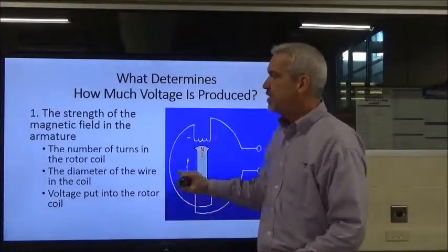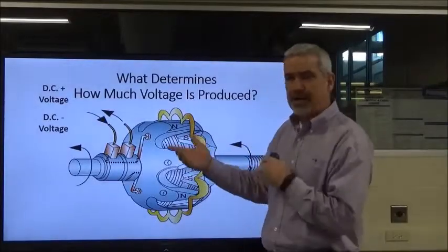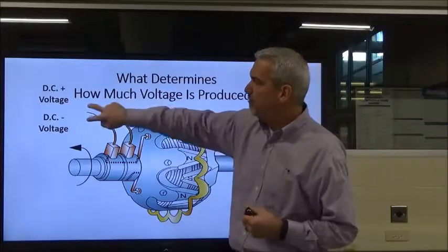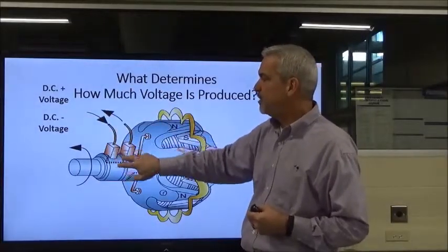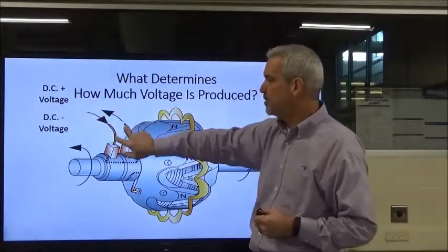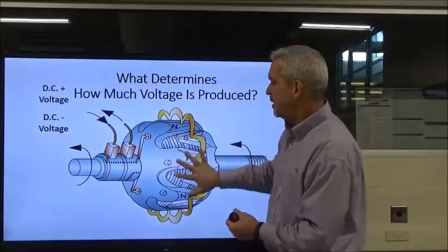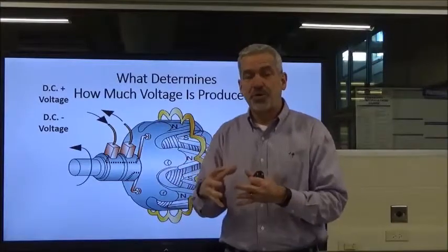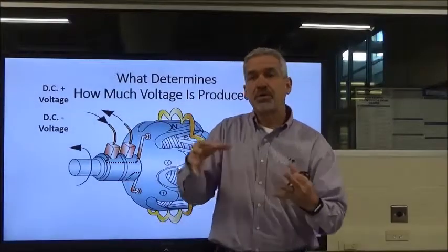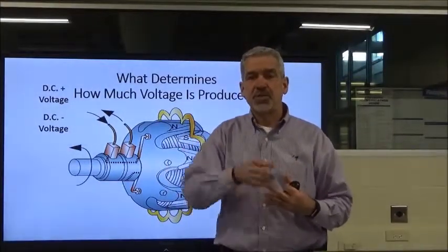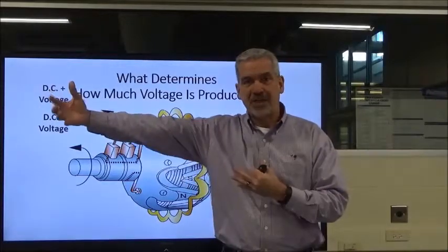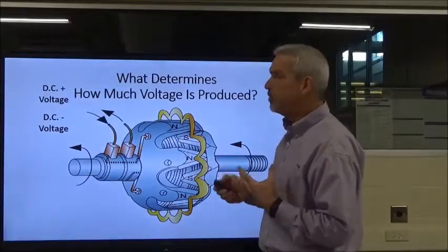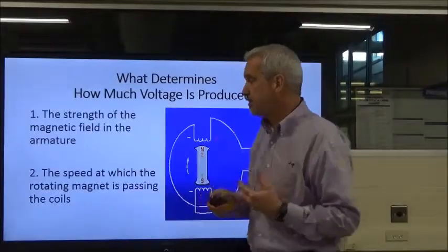Going back to our previous lecture, remember we vary the voltage coming in from our external source into our slip rings and then into our coil. The more voltage we put in there, the stronger the magnetic field in the rotor. The stronger the magnetic field in the rotor, the more voltage is induced in the stator coils, which gives us a higher voltage coming out of the alternator. So those things impact how much voltage we are actually creating.